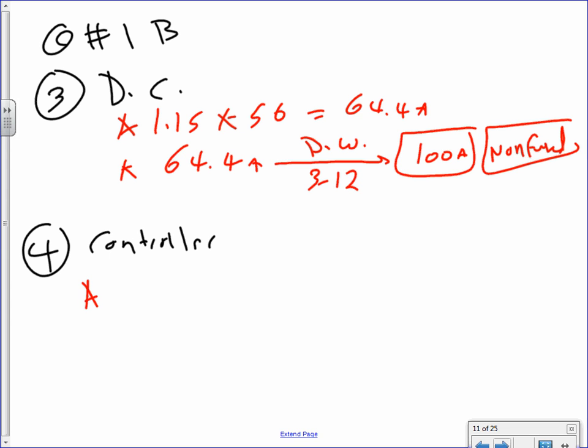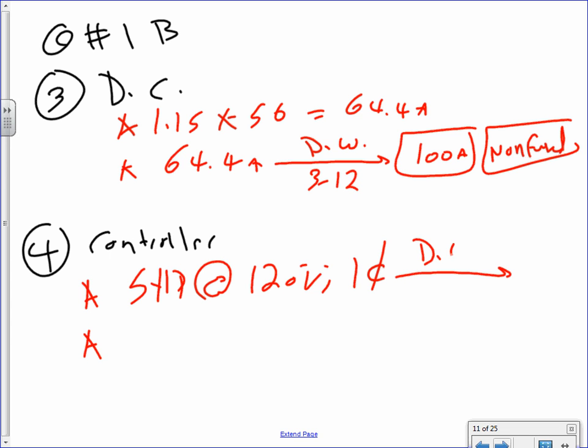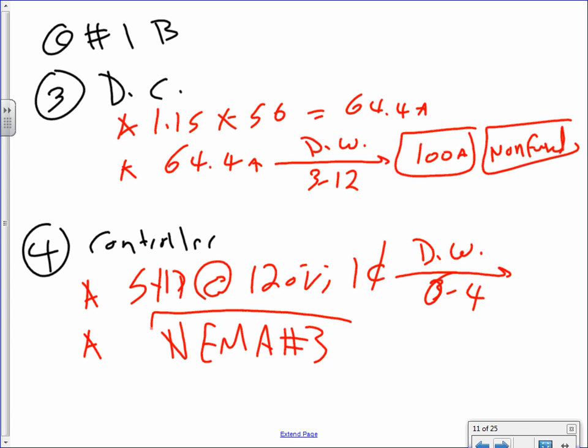Controller, same thing, guys, 5 horsepower at 120 volt, single phase. That's what you do. Derek, you just write this one for me, and you're done. Now, when you have the volt, then you take it from there to the wall, 6-4. That'll get you NEMA number 3. Even so, I can't emphasize enough, guys, these two sizes are too big for the voltage that we're using.